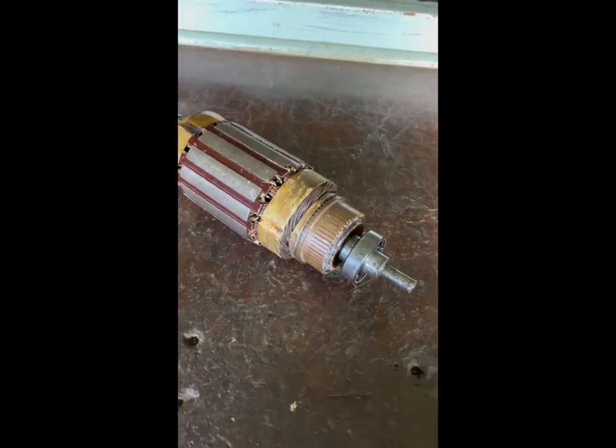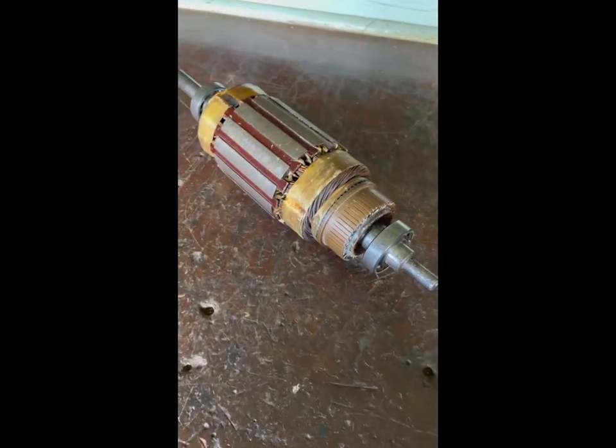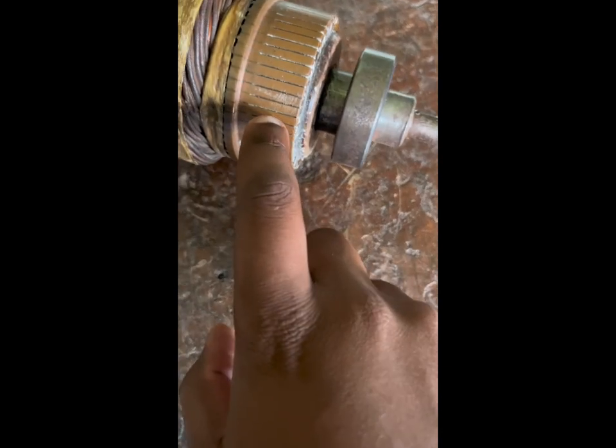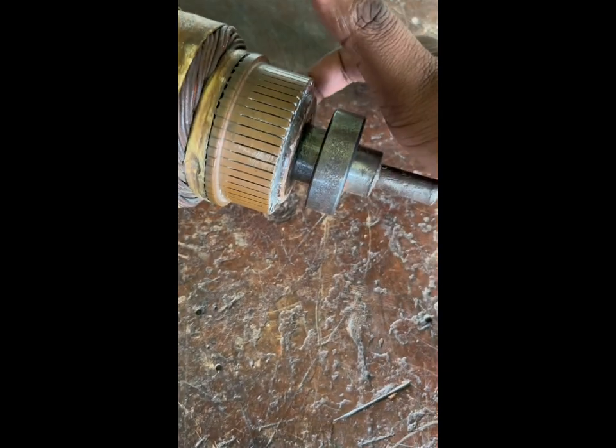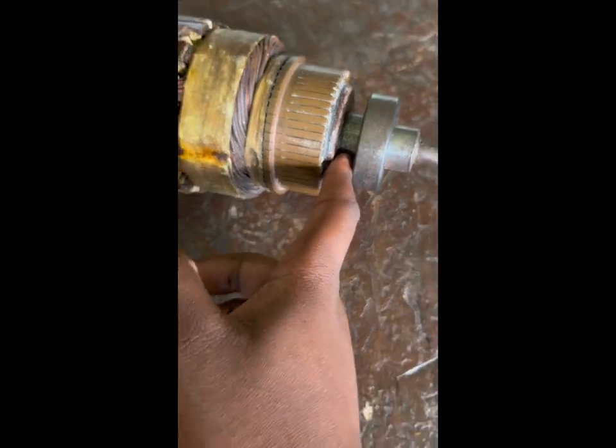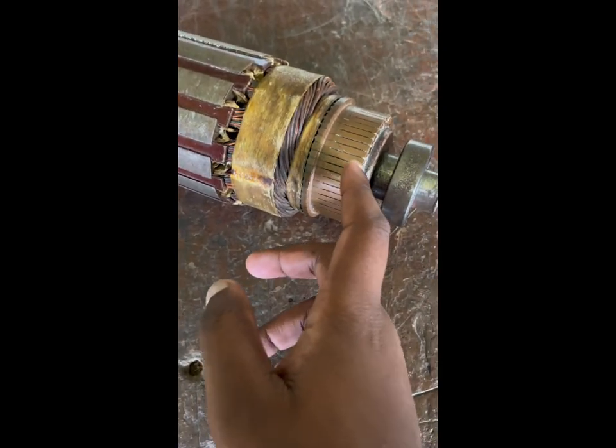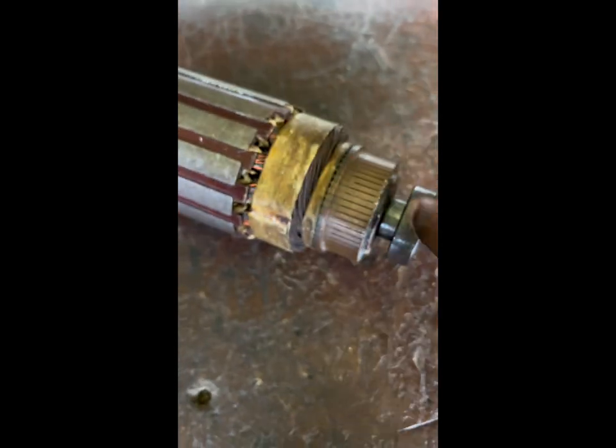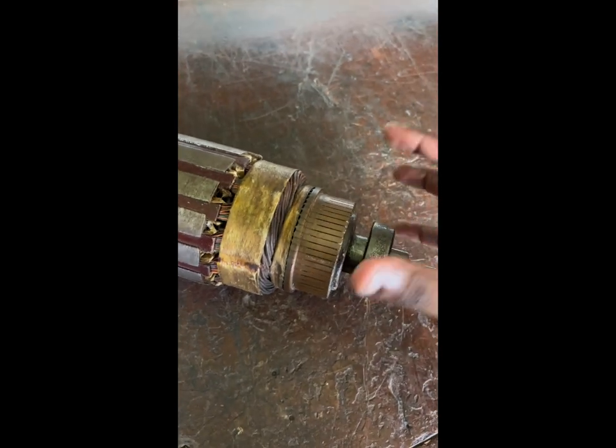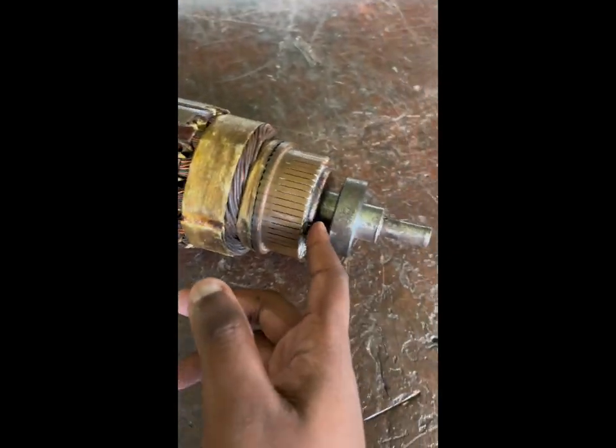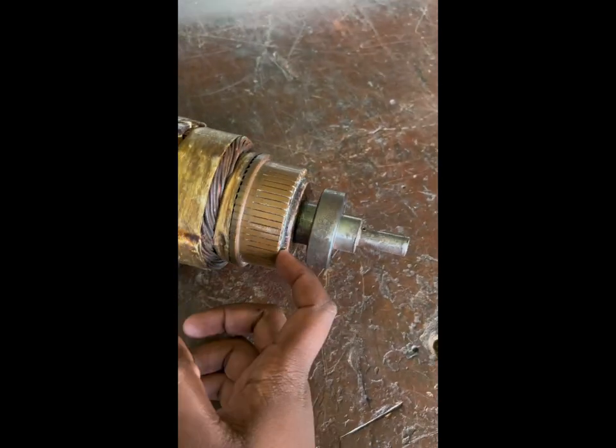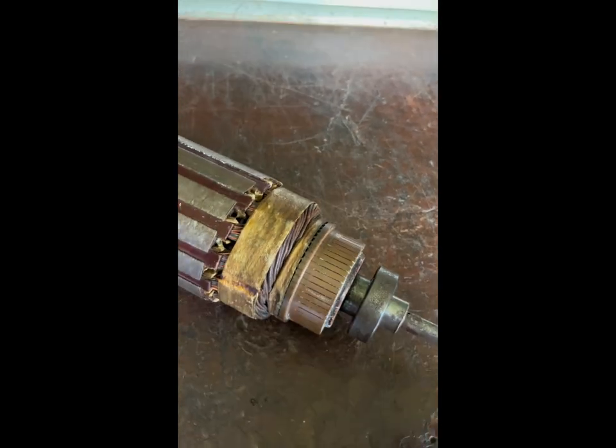Now here is the armature. This is the real armature I have here in the workshop. If we look, these are our commutator segments. They are all cylindrical, but do not just look at them: the commutator segments are insulated from each other. They are also insulated from the shaft, because should they touch the shaft, our electricity will short circuit to the shaft, and the shaft is connected to the casing through the end rings. So should that happen, because of a breakdown of insulation between the commutator segments and the shaft, then we will see the same thing.